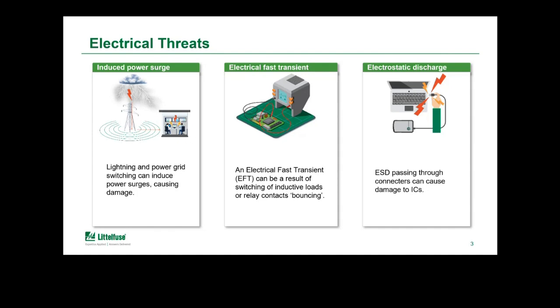Another type of transient event is a switching surge. Turning on and off large inductive loads, such as industrial motors, can cause transient events on cabling. These can result in large voltage spikes because of the inductive characteristics of the circuit and the cabling. Not only is the line where the switching occurred affected, but these events can also be induced onto cables run in proximity to the affected line. This isn't typically as high energy as a lightning strike, but it can still be a very high energy event and can cause damage to end equipment.